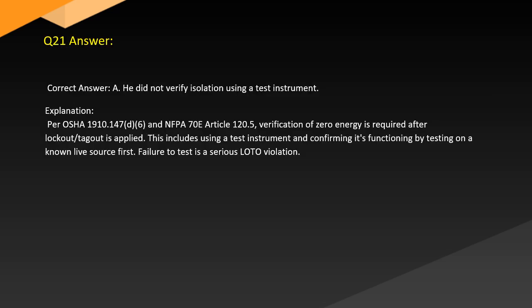Answer. Correct answer: A. He did not verify isolation using a test instrument. Explanation. Per OSHA 1910.147(d)(6) and NFPA 70E Article 120.5, verification of zero energy is required after lockout is applied. This includes using a test instrument and confirming its functioning by testing on a known live source first. Failure to test is a serious LOTO violation.